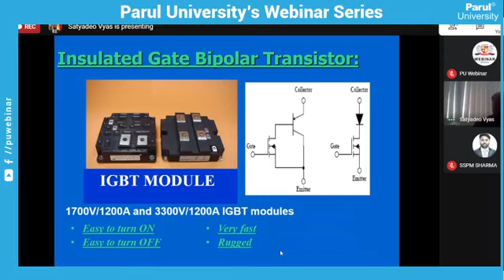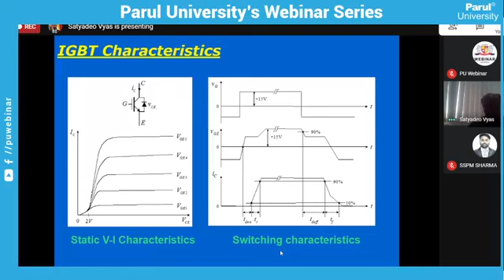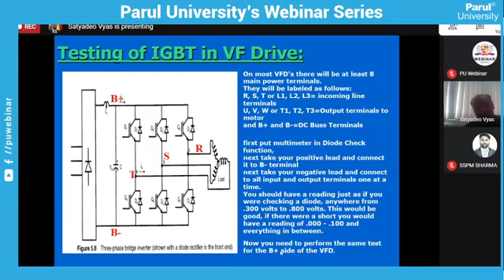So you can see the static VI characteristic and switching characteristics of the IGBT. It's easy to turn on, easy to turn off. Turn off time is very less compared to BJT. Turn on time is also very less as compared to BJT. These are the testing methods of IGBT used in a VF drive. This is the inverter section. 6 IGBTs are used in the inverter section. These IGBTs can be checked with a multimeter. As you check a BJT with a multimeter, similarly, with the same method, we can check the IGBTs.